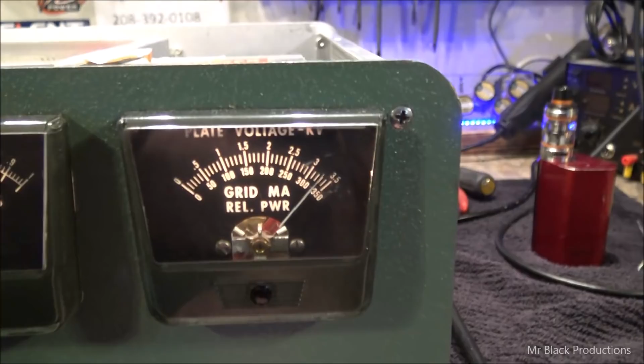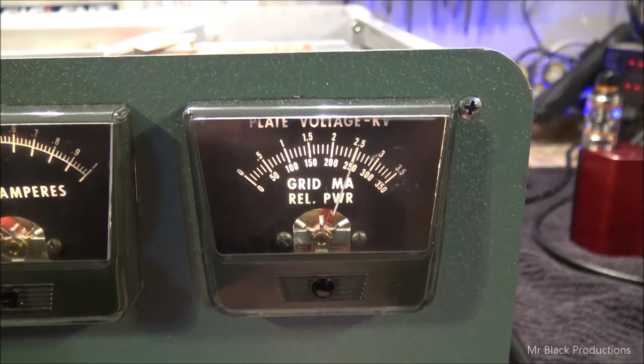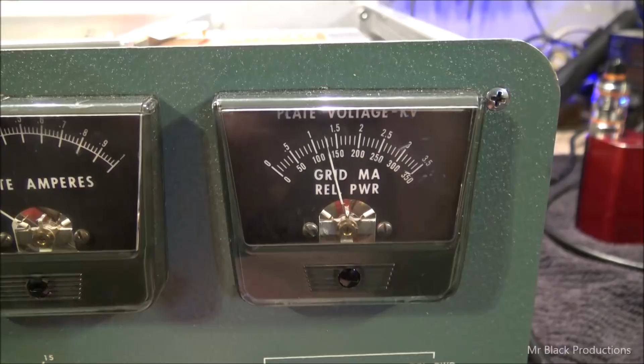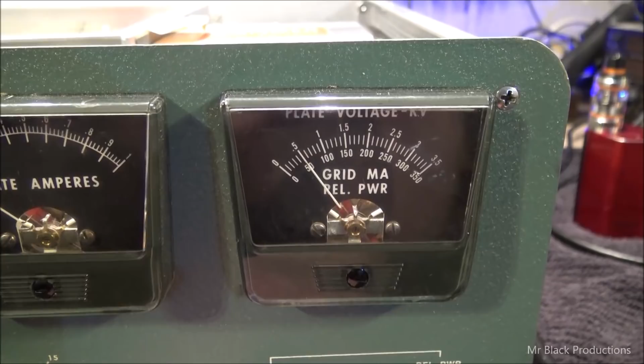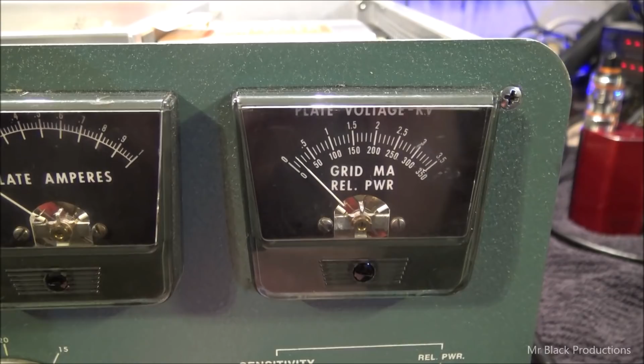Our bleeders are working very aggressively, and what I mean by that is, here's our high voltage at 3,000 volts. Low voltage at 2,500. Look at how aggressive that is. Now as we get down towards the bottom end of the scale, it's going to start moving slower, as you can see. Down to 0. Okay.